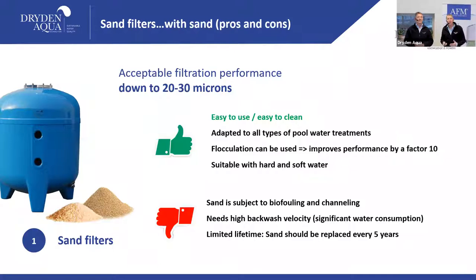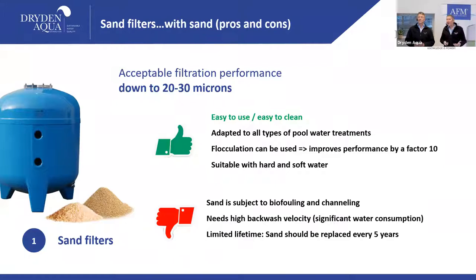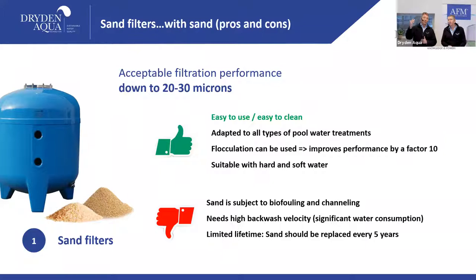Sand filters are very well known, giving filtration of 20 to 30 microns. They're easy and convenient, compatible with all types of disinfection and water treatments, and you can use them with flocculants and coagulants — a big advantage. The downside is sand is a natural biofilter, so it will biofoul and channel over time, performance degrades, and you need a lot of backwash water.